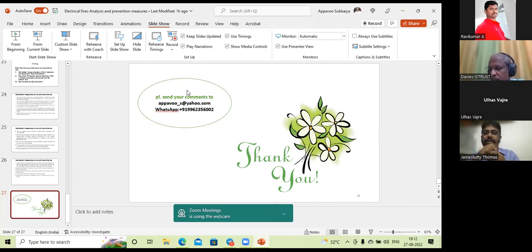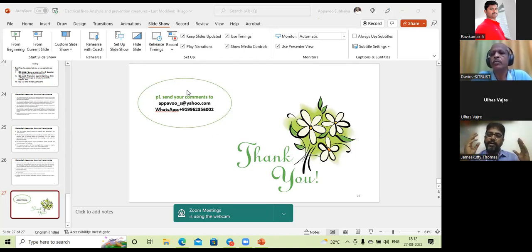Actually, I want to answer Mr. Ravi Kumar on the point Appavoo sir replied to. Lightning protection means a cage, an earth cage, a Faraday cage. If you are inside the cage, you will be safe. Lightning protections are designed through experiments. But early streamer emission was never proved correct. That is why ESE is not allowed as per our 62305 standard and the National Building Code. The actual practice is you should have an air terminal, down conductors, and proper earthing. Then only will it be properly dissipated.